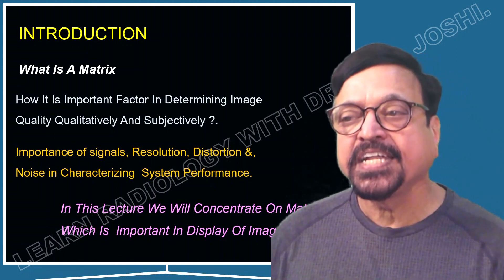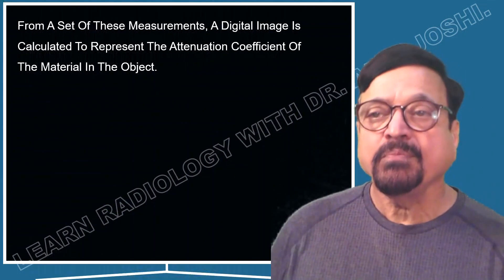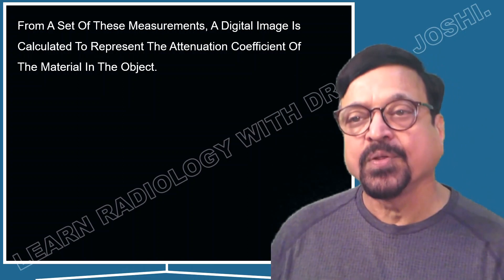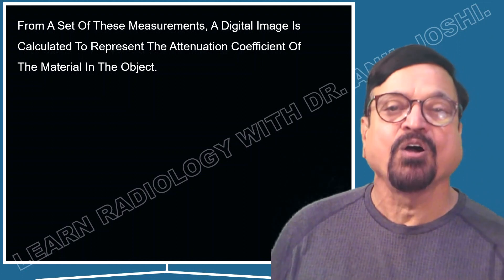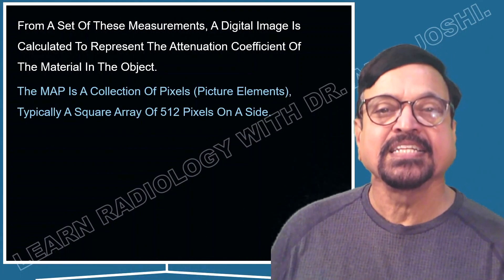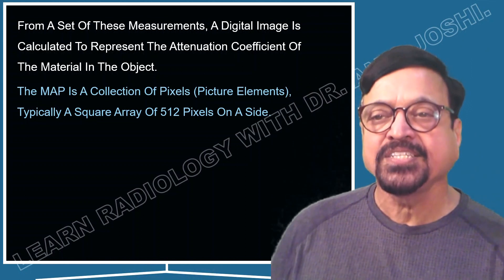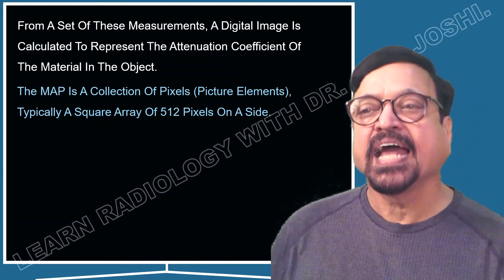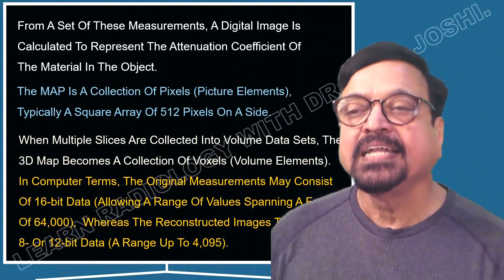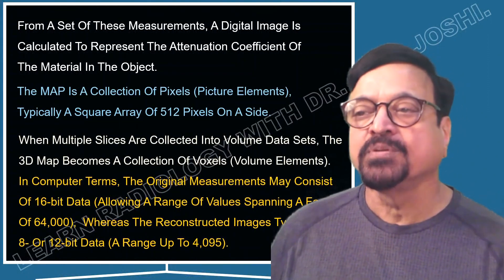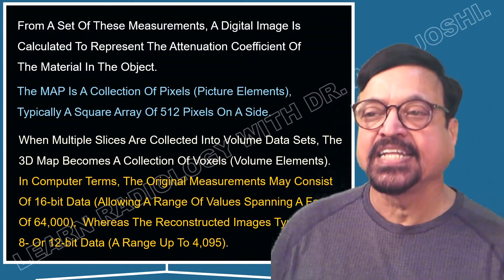In this lecture we concentrate on matrix, which is important in the display of the image. From a set of measurements, a digital image is calculated to represent the attenuation coefficient of the material — or simply the tissue specification. The map is a collection of pixels, typically a square array of 512 pixels on a side. When multiple slices are collected into a volume data set, the 3D map becomes a collection of voxels — the volume elements.